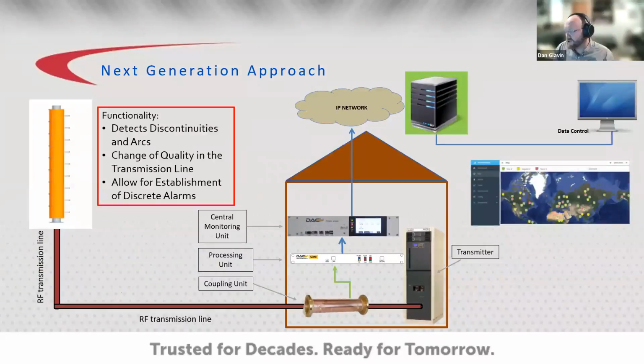The coupling unit consists of 2 injection ports, allowing for a wideband VHF signal to be injected into the system. The design of the injection ports is to couple the VHF signal onto the transmission line while nulling out as much of the broadcast signal as possible. So with that, the RFHawkeye operates independently of the broadcast transmitter itself. It has its own radar transmitter in its box that gets coupled onto the transmission line and sent up to the antenna. Due to the out-of-band nature of the signal compared to the passband of the antenna, the majority of that energy gets reflected back and is interpreted by the central monitoring unit of the system, and the data is both evaluated and manipulated to form a time domain reflectometry response of the system.